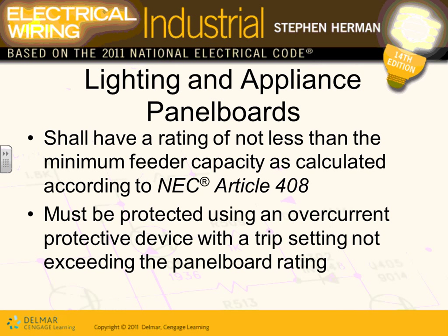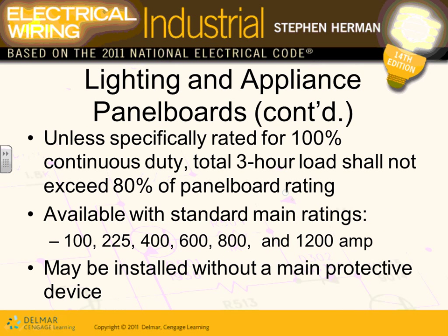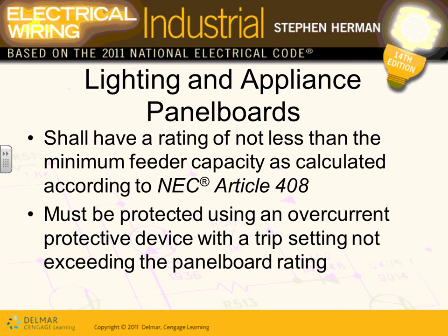That's what this is telling you. You guys have done that with me. Where does it say that? Why did Chad make you do that? Because of Article 408, it tells you when you size a panel, the panel must be able to handle the load fed from that panel, period, done. Can I have a thumbs up, Chad? We fully understand how to size a panel and that I can't feed more load from the panel than the panel can handle. So if your panel's 125 amp and your load is 200, can you feed a 200 amp load from a 125 amp panel? No. Why? Well, if you don't know, because the code says so.